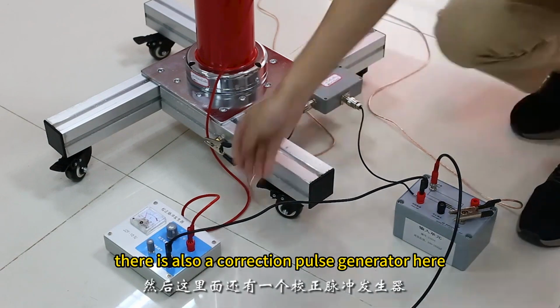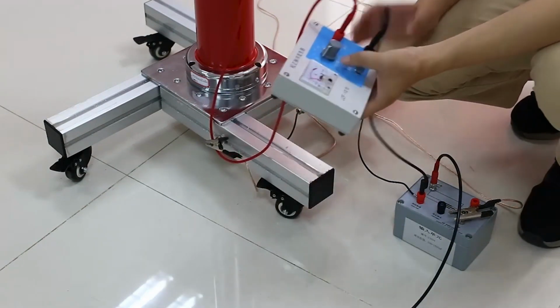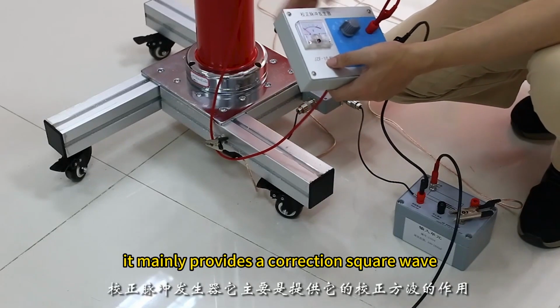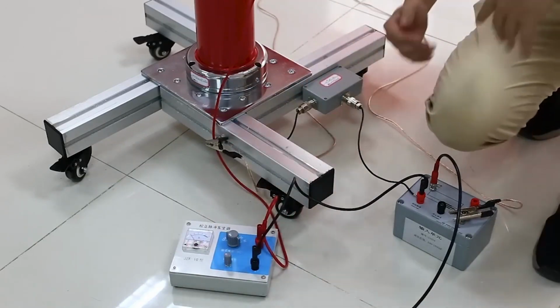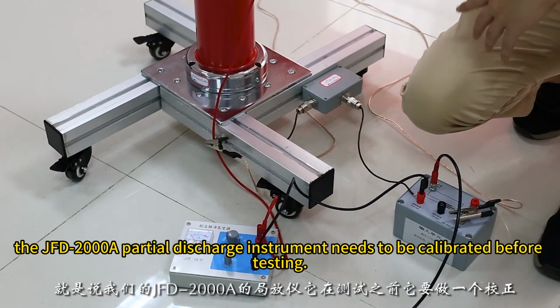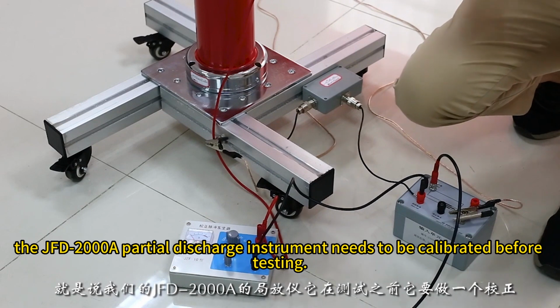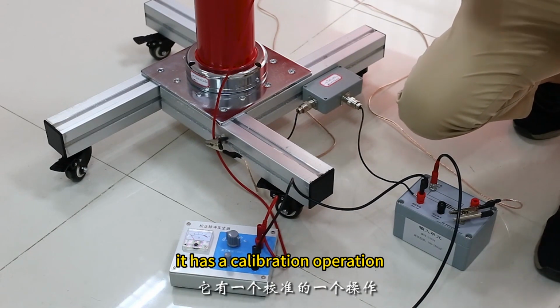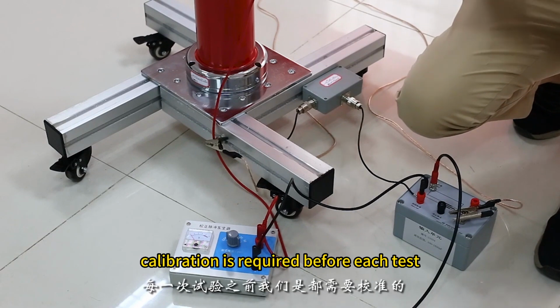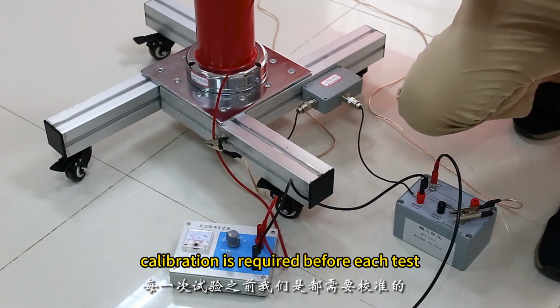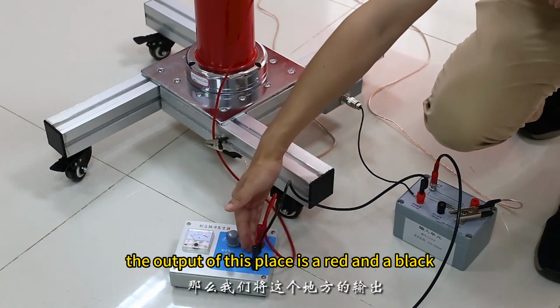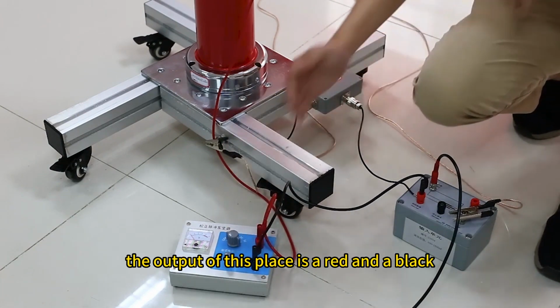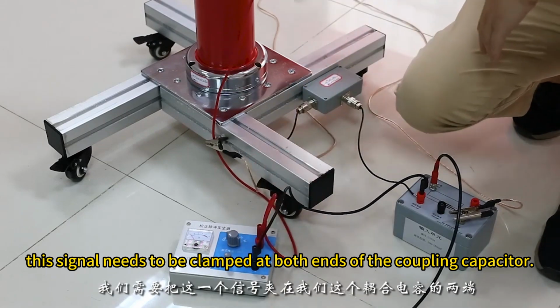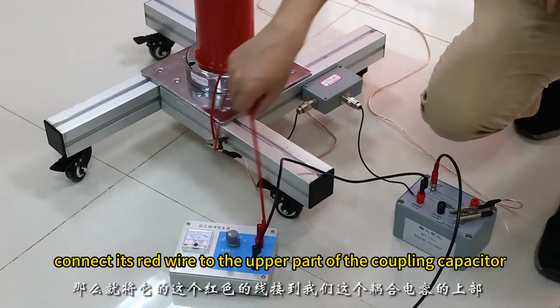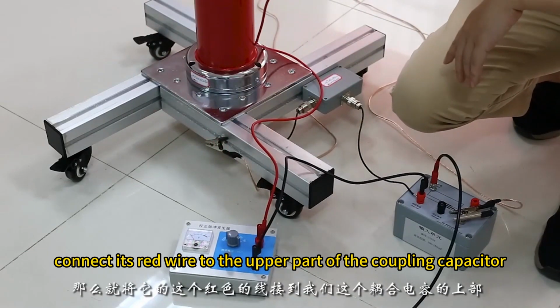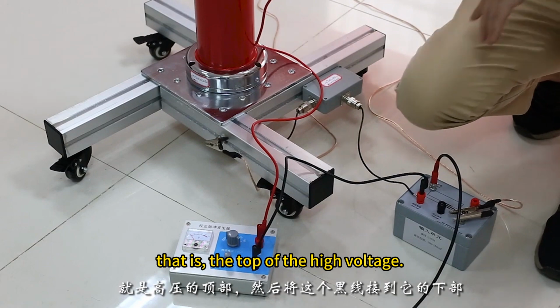There is also a correction pulse generator here. It mainly provides a correction square wave. That is to say, the JFD 2000A partial discharge instrument needs to be calibrated before testing. It has a calibration operation. Calibration is required before each test. The output of this place is a red and a black. This signal needs to be clamped at both ends of the coupling capacitor. Connect its red wire to the upper part of the coupling capacitor, that is, the top of the high voltage.